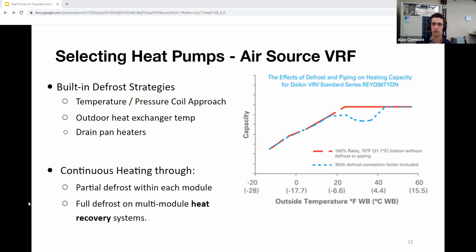Now, we talked about the blue line on the diagram, and how it takes into account defrost for the heating capacity. Well, it's actually possible to get continuous heating during defrost. If you have two units side by side, one unit can be in defrost while the other one is still heating, which will provide refrigerant to the building. So it's still possible to get continuous heating during defrost with these types of machines.